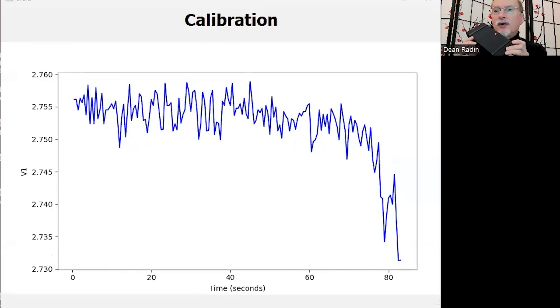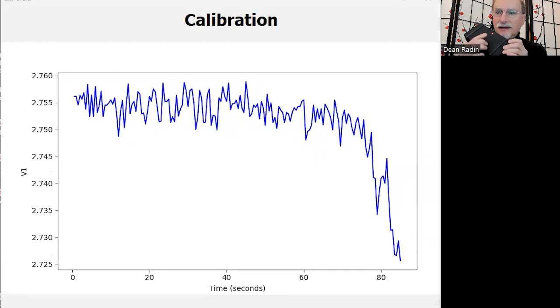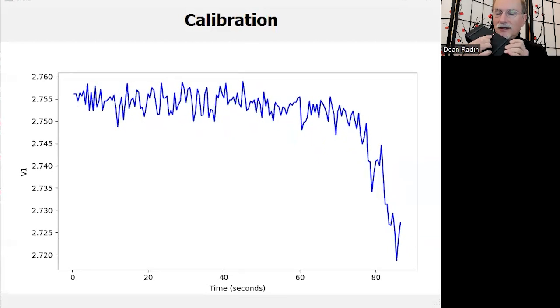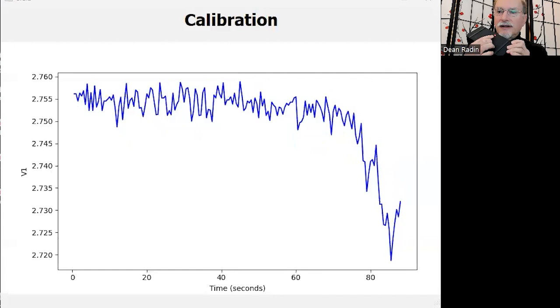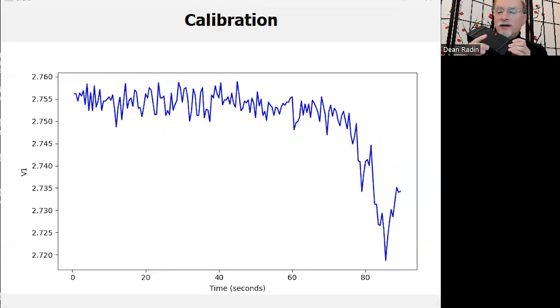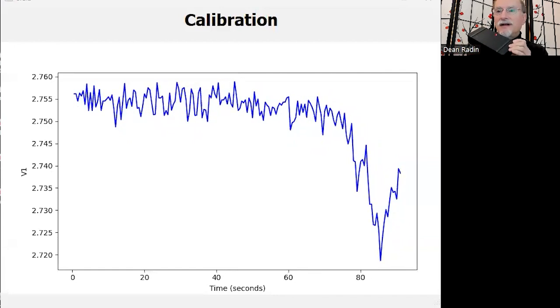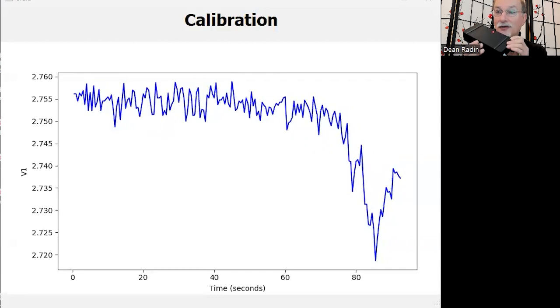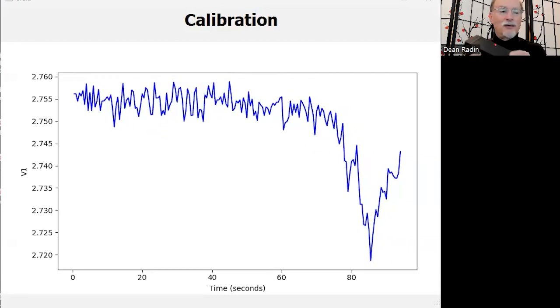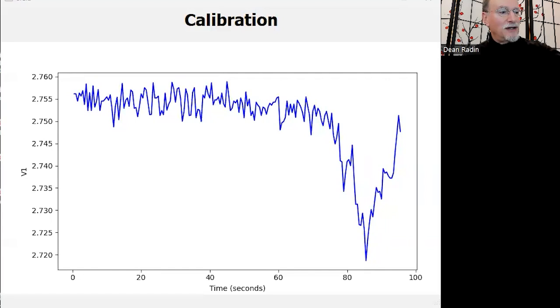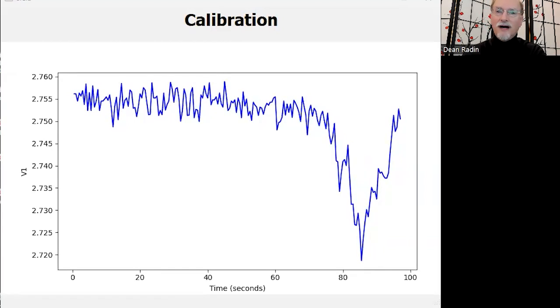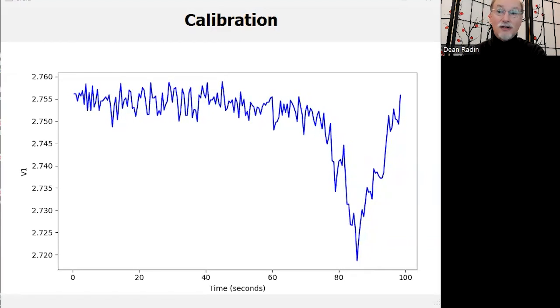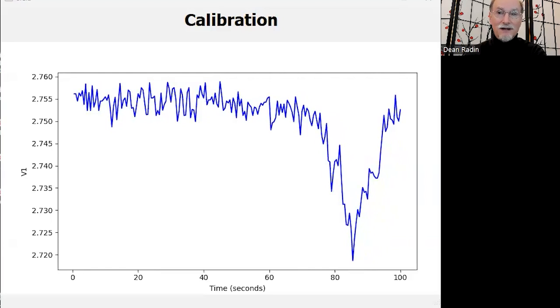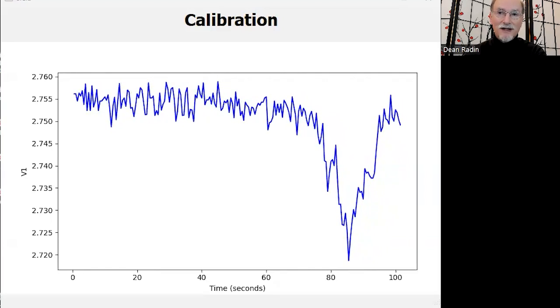One thing I'll show you while we're watching the screen there is that the light has turned red, which indicates that the system is in calibration mode. Also notice that the signal itself changed pretty dramatically when I picked up the box to show you this. This is one of the reasons why when you do this experiment, not only should the general environment be pretty quiet, but do not touch the box. The optics are very, very sensitive.